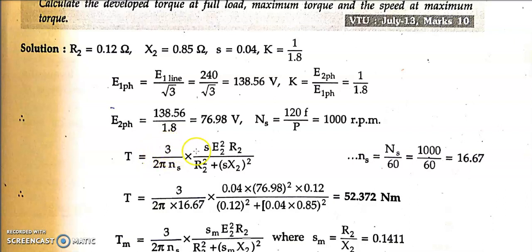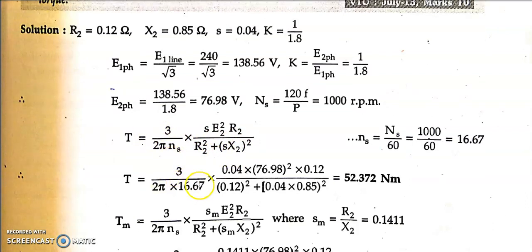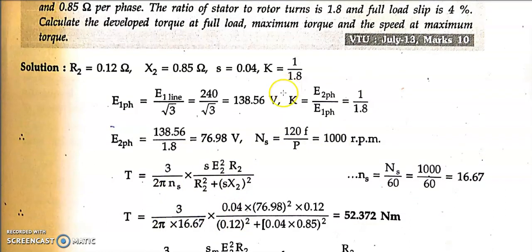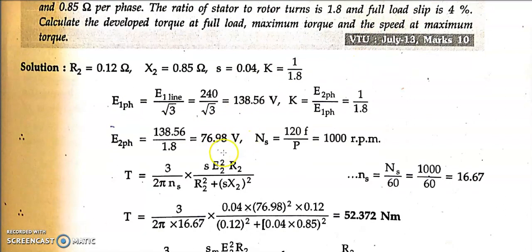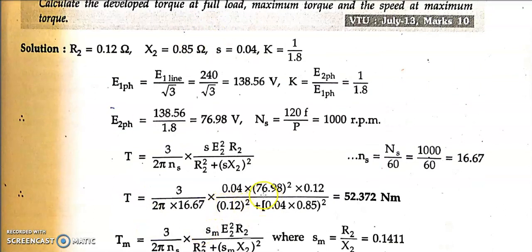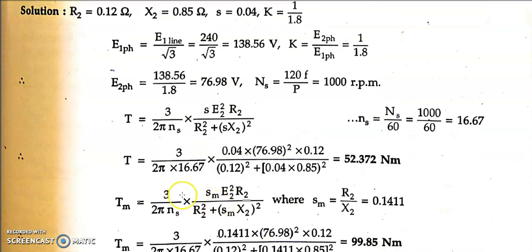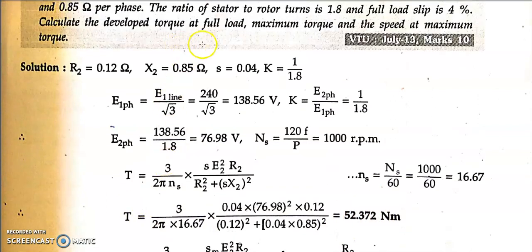The general torque formula is T = (3 / 2π·ns) × (s × e2² × r2) / (r2² + (s·x2)²). Substitute s = sfl = 0.04, e2 = 76.98 V, r2 = 0.12 ohm, x2 = 0.85 ohm, ns = 16.67 rps. The full load torque Tfl = 52.372 N·m.